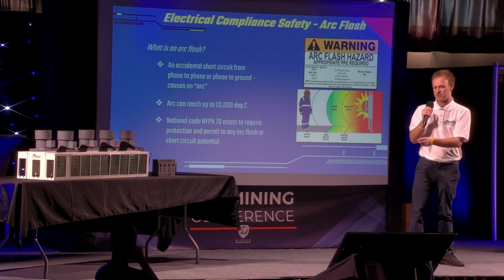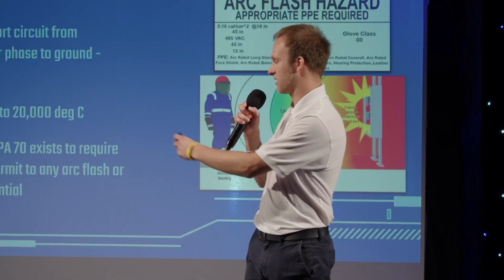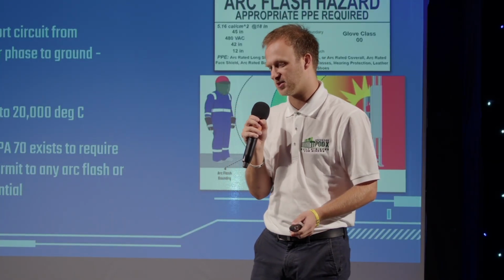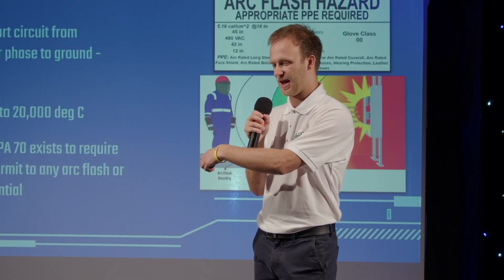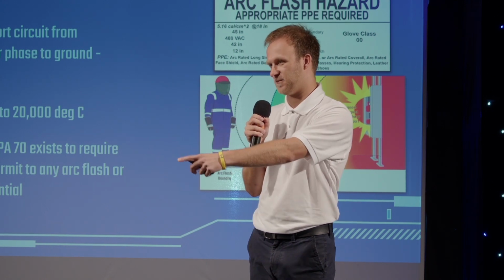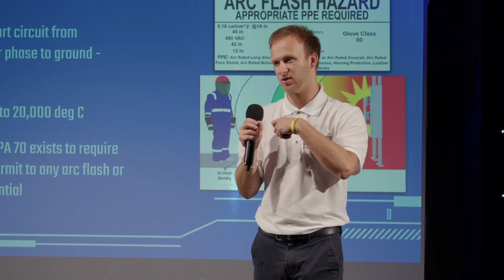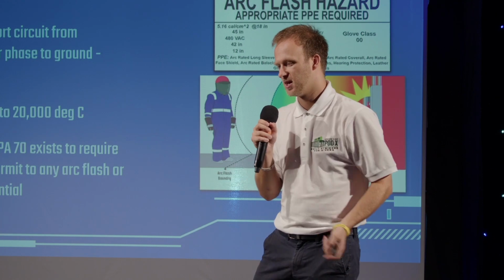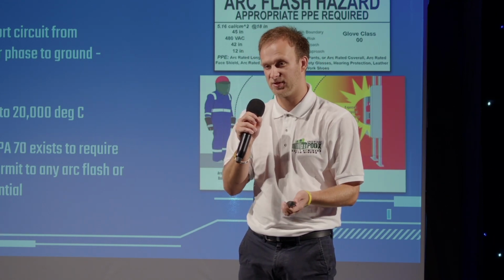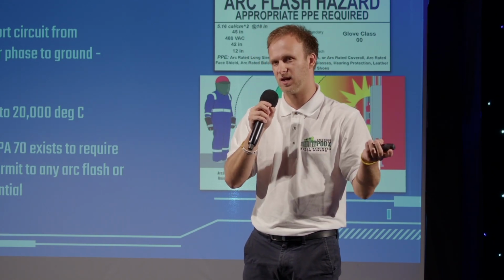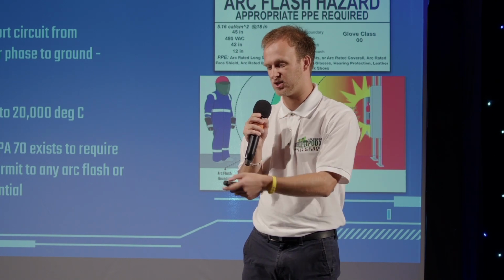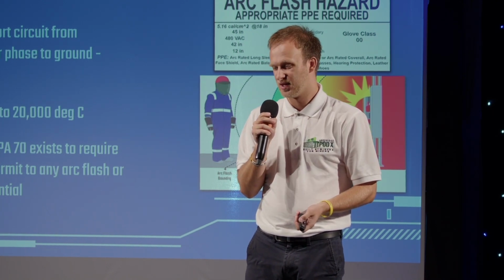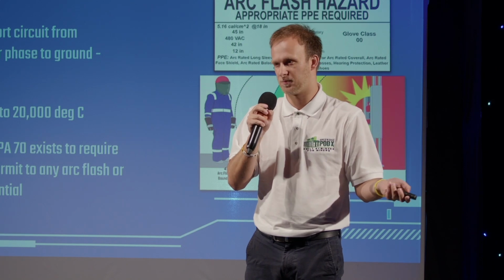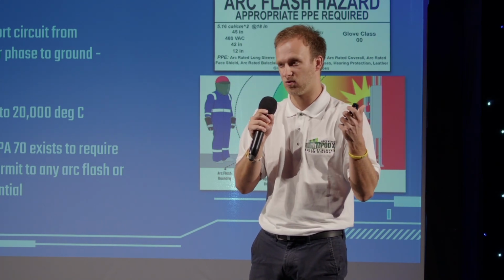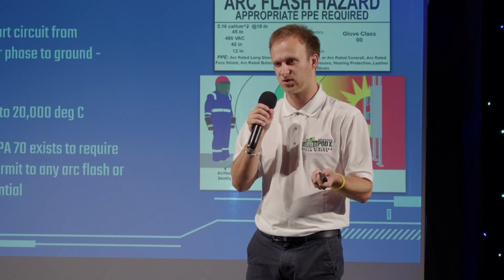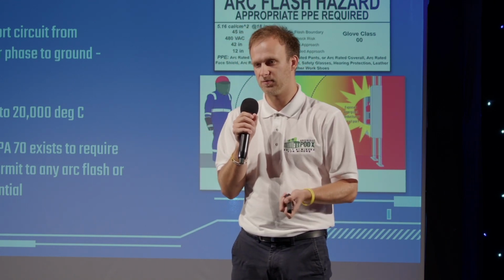But a lot of the problems that could arise are safety issues like arc flash. If you don't know what arc flash is, to put it short, it is basically an accidental short circuit from phase to phase or from phase to ground. And when that happens, the short circuit creates an arc, which is like a lightning bolt. That arc can reach about 20,000 degrees Celsius, which is extremely hot, enough to burn you for sure, send you flying back, or even be life-threatening if the potential is really high. So it's something that you really need to be aware of.